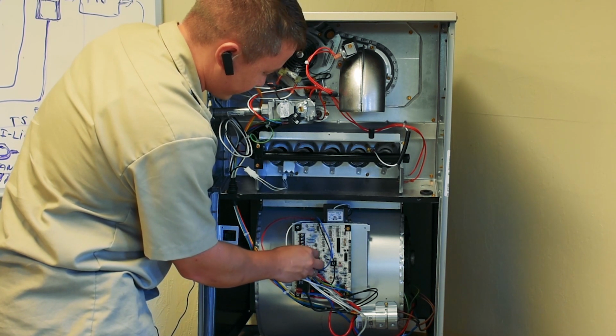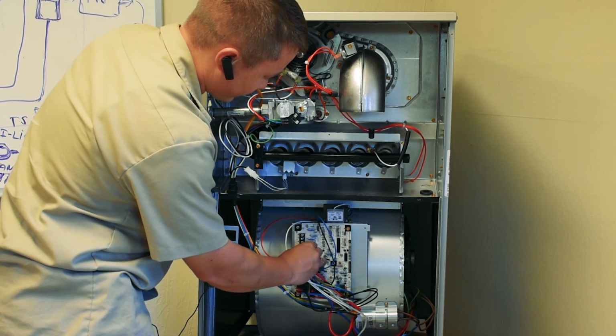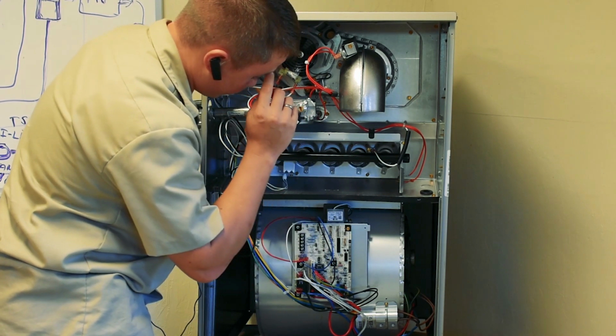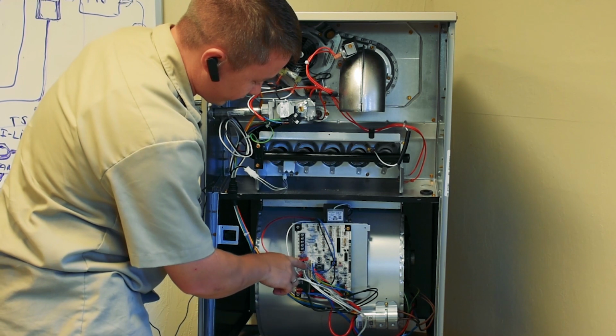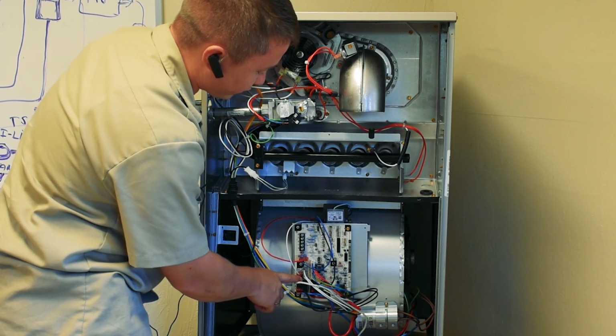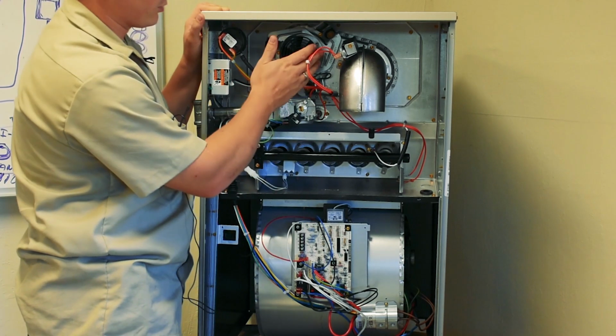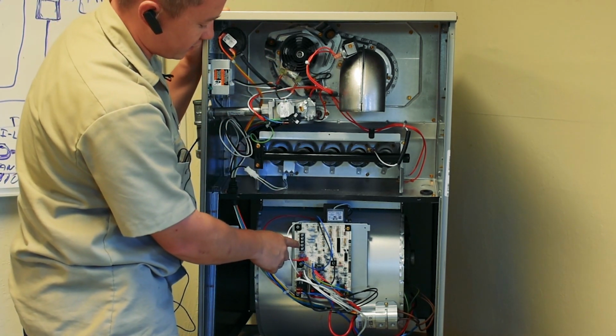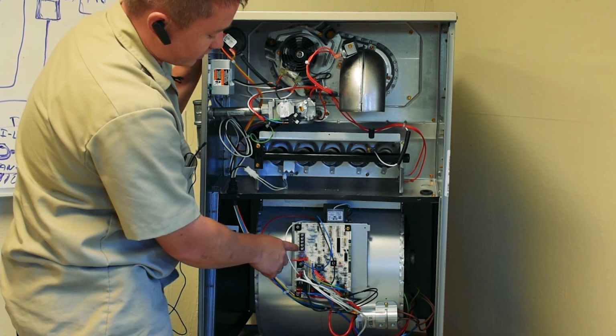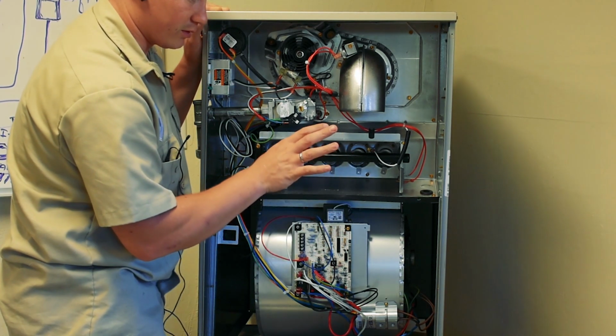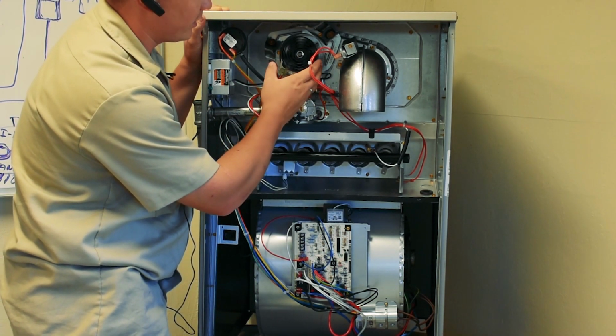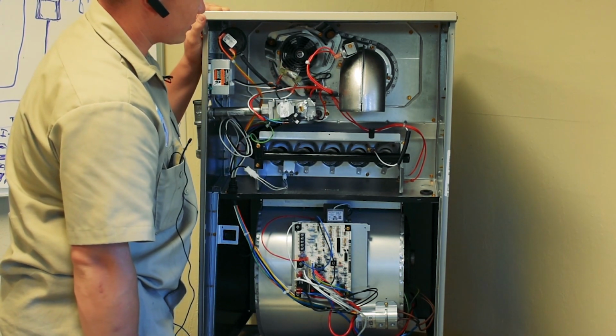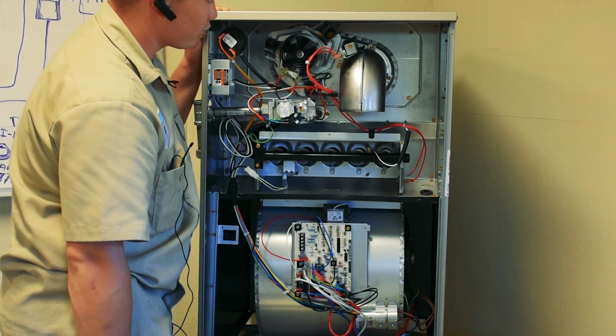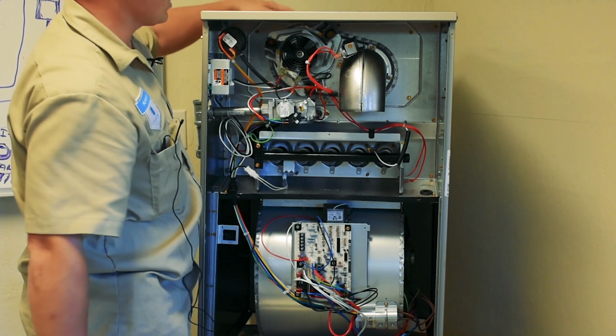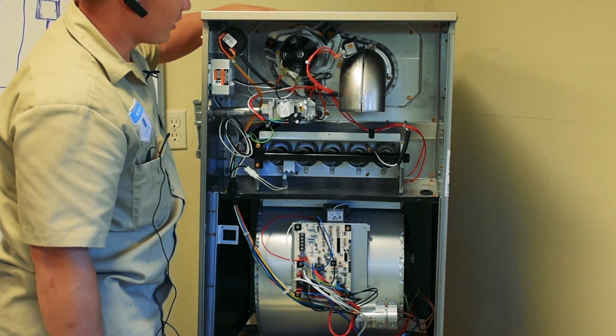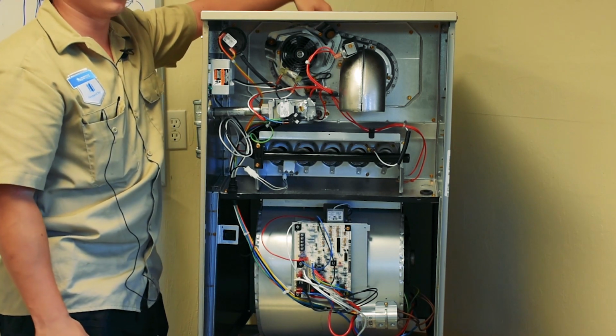Okay, when you turn on the heat on the thermostat, the first thing that will run is the relay on the control board which gets power to the inducer motor. When you turn on the W and R terminals on the wall thermostat, it will run the inducer motor immediately. The next thing, because it's increasing the pressure inside the room where we have the heat exchanger, it's actually right here.